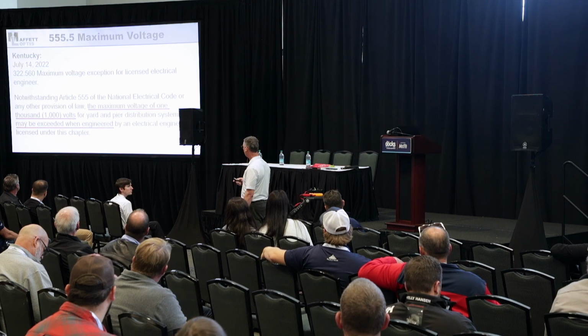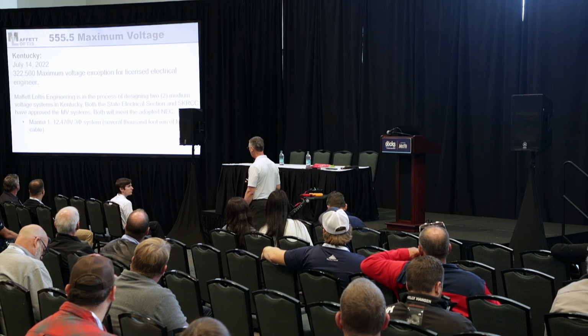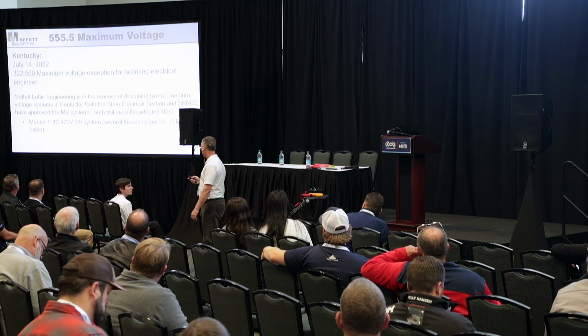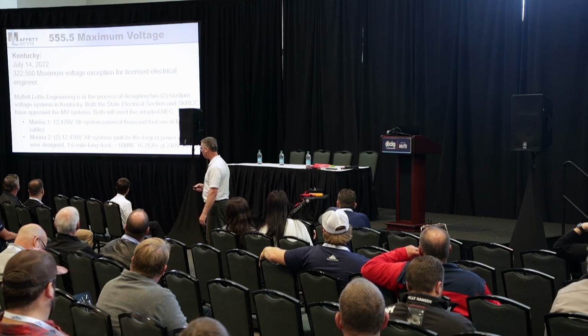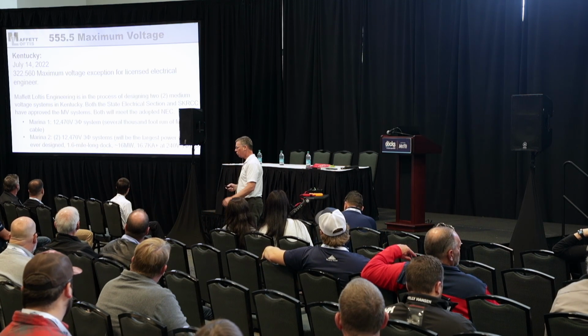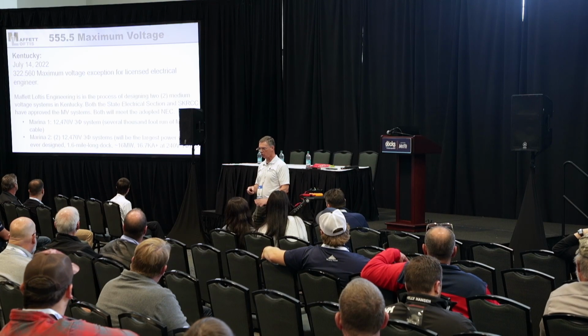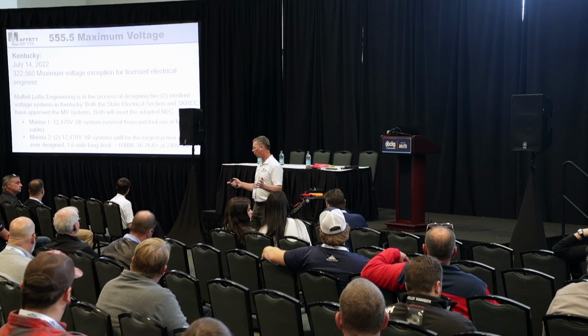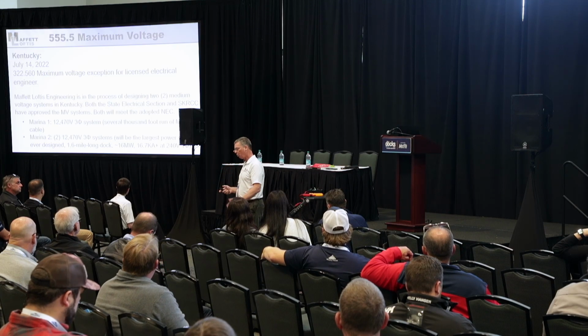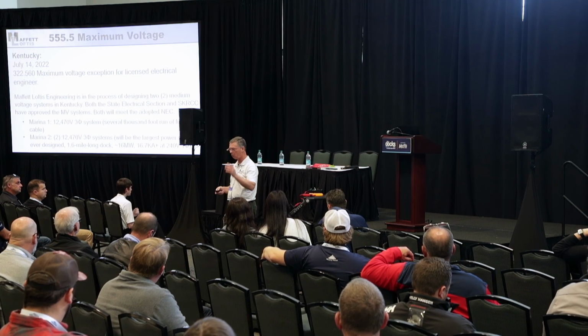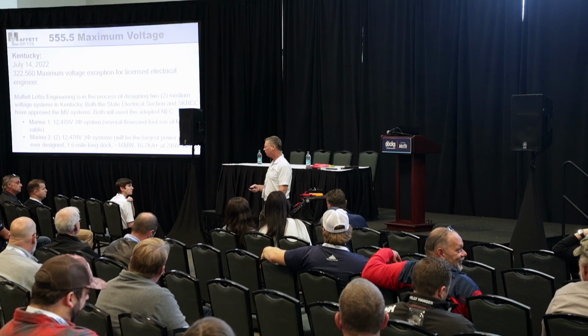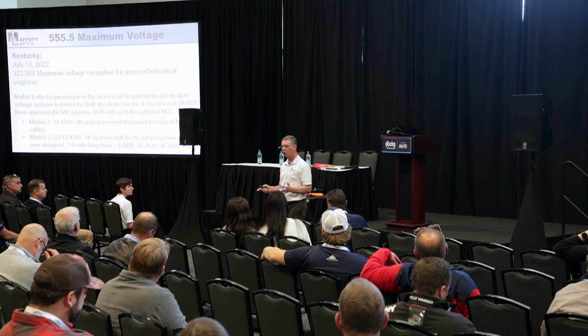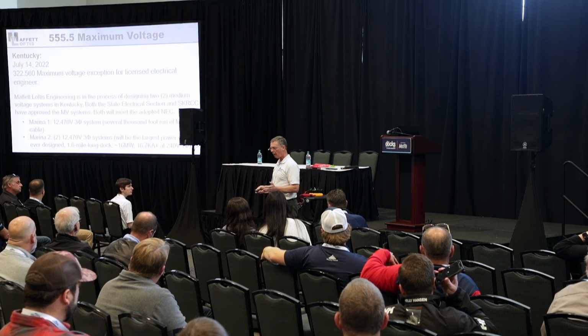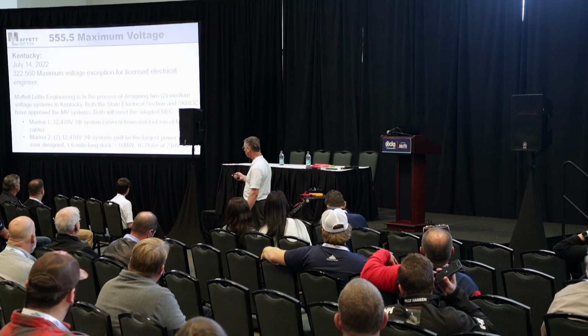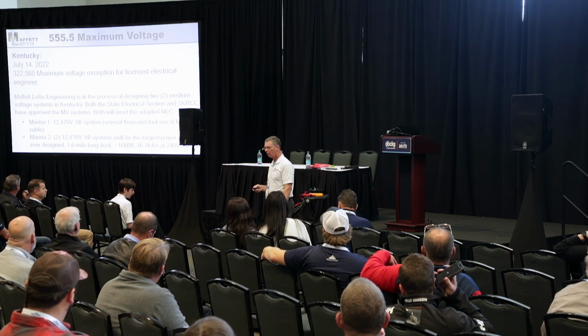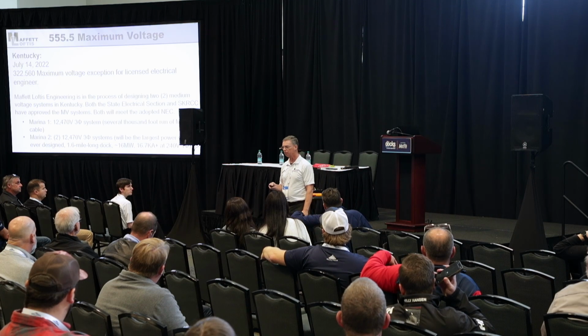In Kentucky, I'm doing the biggest power system I've ever done in my life. It's about a 16 megawatt system with a 1.6 mile long dock. Think about that distance, and about every 40 feet we're putting in 200 amps along the whole 1.6 miles. That's a very strong candidate for medium voltage, and there's no other way to do it. In fact, that project was one that prompted Kentucky to pass the law allowing medium voltage.